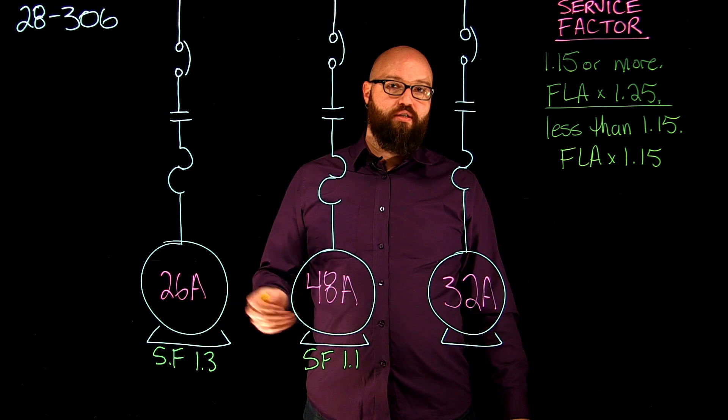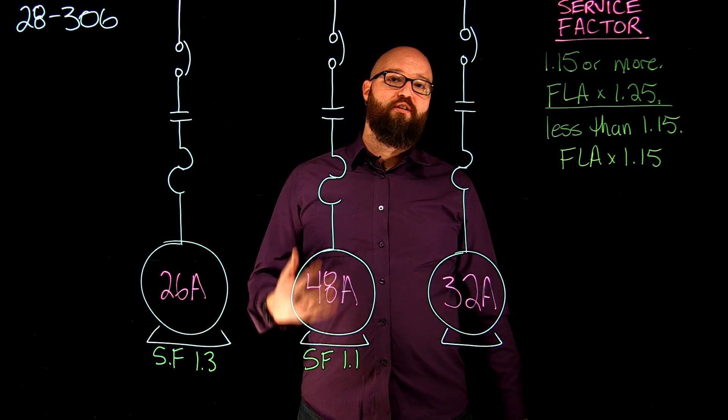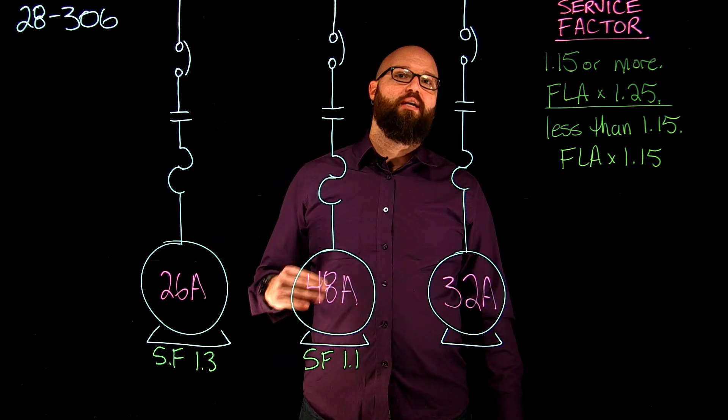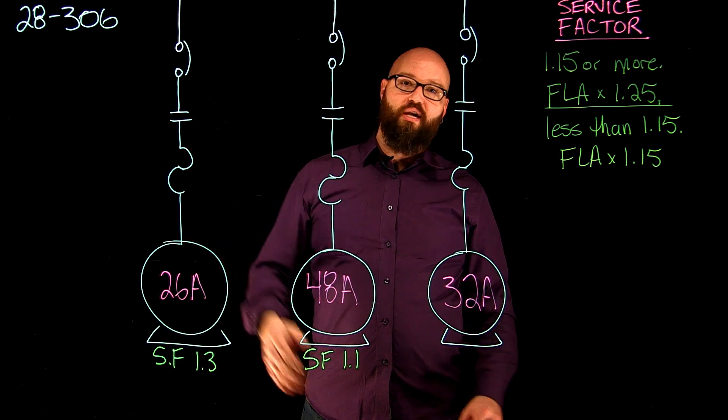If it was an adjustable, I would adjust it up to whatever number I've calculated. If I was purchasing one that had a predetermined value, I would go down to the next available size, as I'm not allowed to exceed the values from 28306.